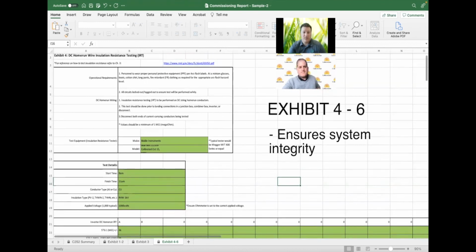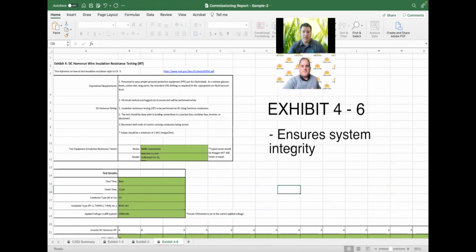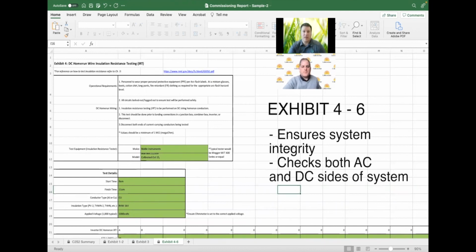Yeah, so 4 through 6 is really, on the DC side, was it installed right? On the AC side, was it installed right? And that usually, depending on the equipment or the optimizers or the inverters installed, may or may not include a Megger test. Basically you're trying to see: are there breaks in the wire? Are there nicks in a conduit that could cause a ground fault? Really, is the wiring intact and all the connections nice and tight, both on the AC and the DC side.